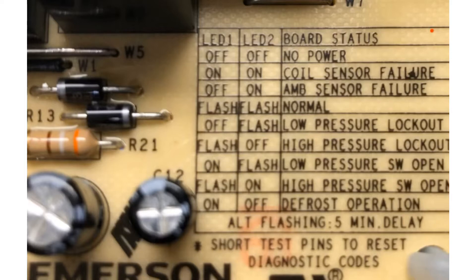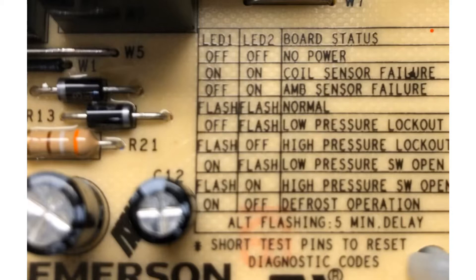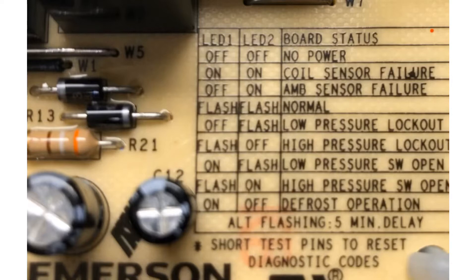If they're both flashing that's normal operation. We have low pressure lockout, high pressure lockout, low pressure switch open, high pressure switch open, and defrost operation. The alternating flashing is going to be our five-minute delay. That can be bypassed by shorting the test pins. Also you can short the test pins to clear a fault code. That's going to then throw it into a five-minute delay and then you just short the test pins again. Just shorting it one second will do that.